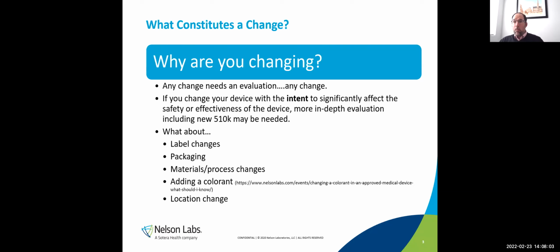Me personally, most of the time, the materials are pretty safe. We've been using pretty much the same materials for a very long time. So it's not like we're seeing new materials come out that cause a high level of risk. For me, the thing I'm mostly concerned about when I look at changes or even a full biocompatibility evaluation is the processes. What are we leaving on these devices through the process that could be impacting our patients? So for me, the process is probably the thing I focus on more.